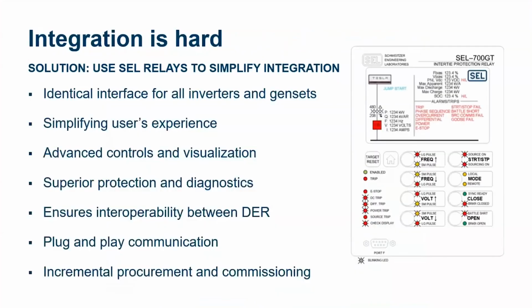I was at a conference recently in California. The number one reason for microgrid failure in California was identified to be integration. Integration is hard. Integration means pulling together inverters, paralleling inverters with generators, paralleling inverters of different manufacturers, point of common coupling discussions with the utility, making sure your relay settings coordinate with the utility, testing everything, dealing with firmware. It's really challenging. This takes skill, but we use relays to simplify our work.